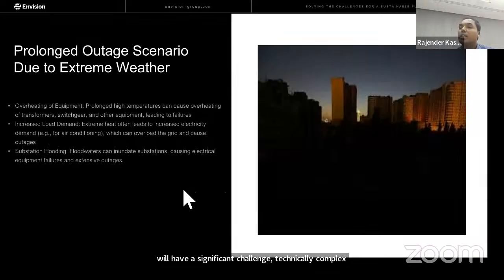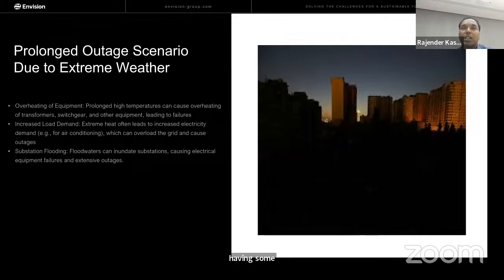And one more problem for the MENA region, like we recently saw in 2018 in Azerbaijan, is that a grid collapse happened. A grid outage occurred for the country, and it took around one or two days to restore to normal condition. It was because of the temperature rise. Even at 40-degree temperature, the thermal boiler fans of the biggest thermal generator in the country failed, and due to that, a fire broke out in the thermal plant. It caused the biggest disruption in the country.